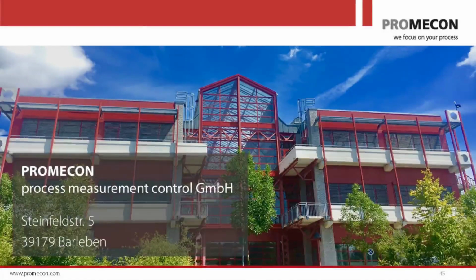So these are the 2 methods, and what I can only invite you, if you have questions about your boiler and your air, and you have real interest, you could take a couple of screenshots, as I just mentioned, either the trend of the airflows and dampers for secondary air, or the values that I've just given you: feeder, airflow, and delta T over your mills. And you can send us those screenshots, and we can do the analysis for you.